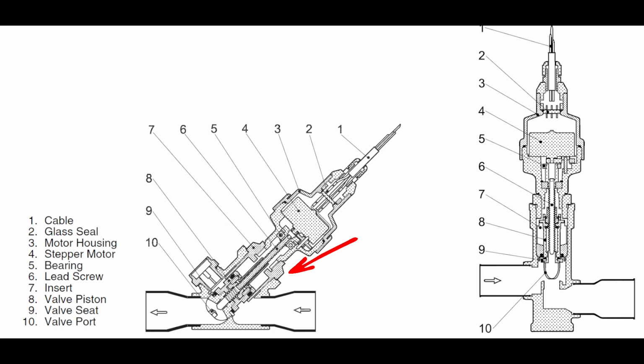A loss of charge, which typically you're going to see a high suction superheat or a high discharge superheat because you're running a low saturation. So most of the time, if you see a loss of charge fault, then it's because your suction or your evaporator saturation got too low and it got down below freezing or got really low really fast, which would indicate that we don't have enough refrigerant in the system if everything was working properly. Now, your first step in there should be we need to verify our valve operation.